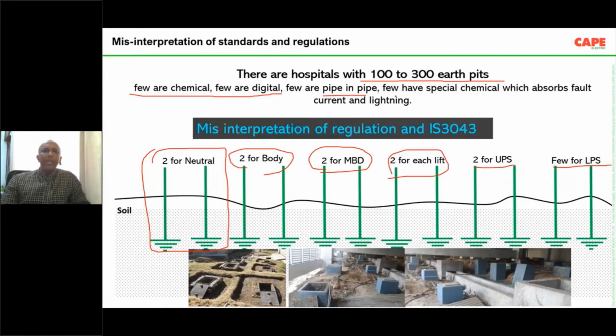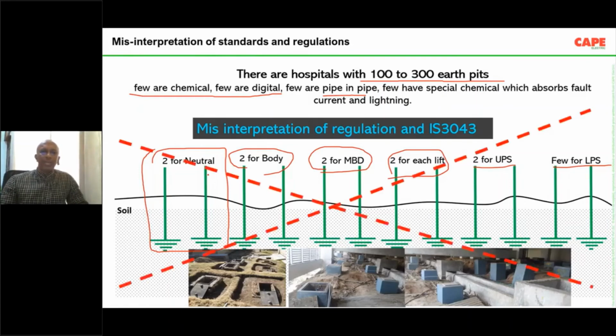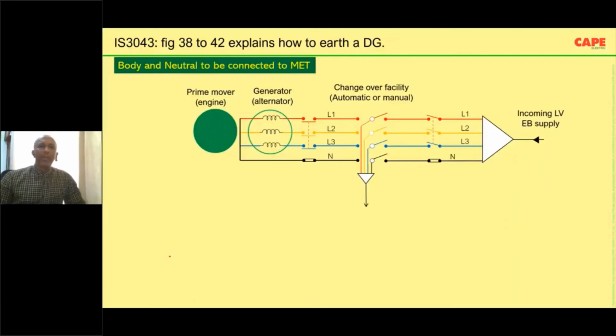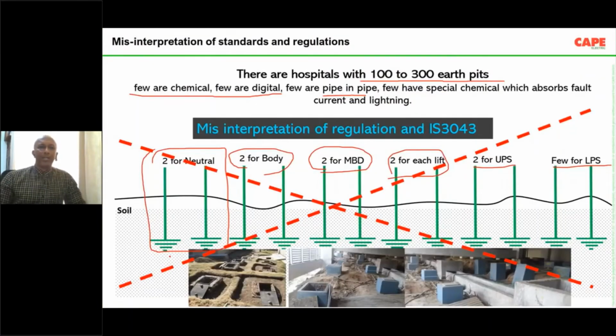Actually, earthing has nothing to do with these earth pits. Earthing is a subject which has nothing to do with these earth pits in low voltage engineering. In low voltage engineering, the method of earthing is totally different. What do we mean by earthing in low voltage? As I said, I repeat again, making separate earth pits under the soil and interconnecting everything under the soil is a big mistake. You don't need it. It's a misinterpretation of the standard and regulation.